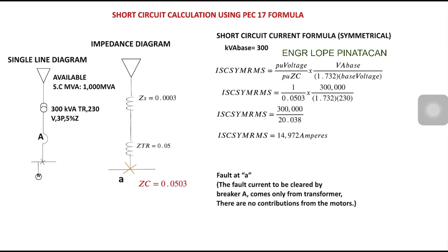So itong calculation nito, dahil dito tayo nag-short sa point a, so we will neglect the motor load. So now the recommended circuit breaker to be used on this circuit is 15,000 ampere interrupting capacity, so 15 kAIC. So that is the minimum circuit breaker to be used on this circuit, kasi kung masyadong mababa baka sasabog yung breaker. So kaya dyan importante ang short circuit calculation.